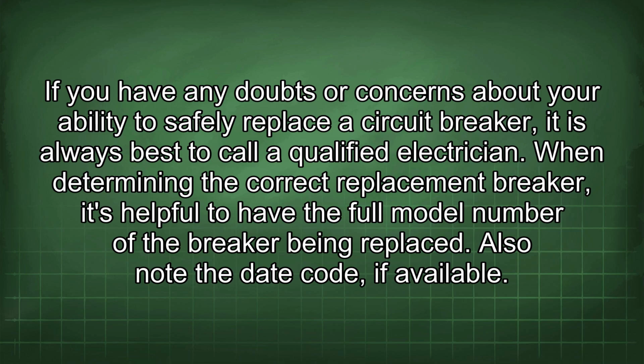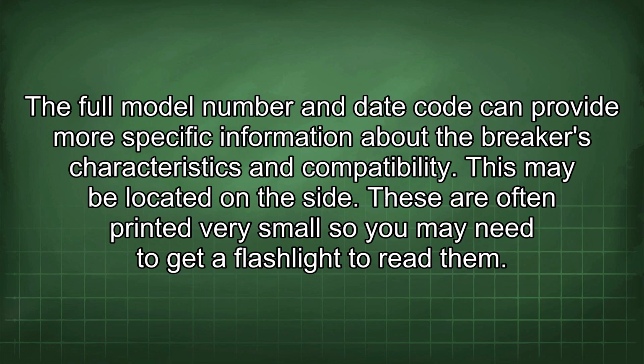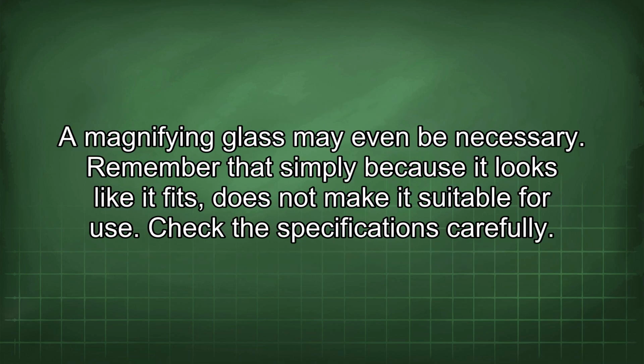When determining the correct replacement breaker, it's helpful to have the full model number of the breaker being replaced. Also note the date code if available. The full model number and date code can provide more specific information about the breaker's characteristics and compatibility. This may be located on the side. These are often printed very small, so you may need to get a flashlight to read them. A magnifying glass may even be necessary. Remember that simply because it looks like it fits, does not make it suitable for use.